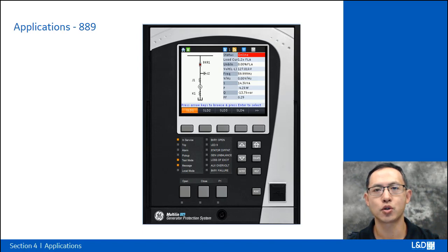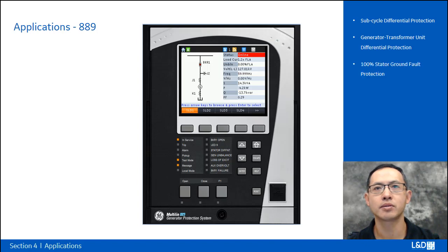889 has been designed for the protection, control, and management of generators and associated unit transformers in critical utility and industrial applications. 889 provides fault clearing operating up to sub-cycle speed by utilizing high-speed dual-slope differential protection for detecting and clearing stator faults. 100% stator ground fault protection is provided in 889 for both high-resistance ground systems and low-resistance ground systems or hybrid ground systems. 889 offers a comprehensive generator health report that provides an easy-to-read snapshot of generator health and operating condition, and advanced generator monitoring and diagnosis, including the analog inputs of bearing vibration and excitation current.